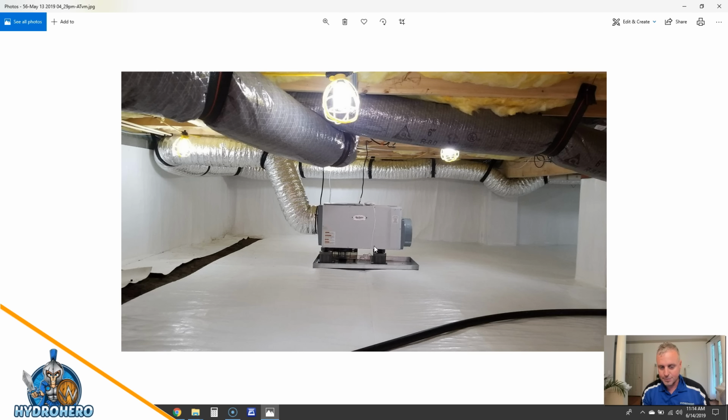We got this dehumidifier in here, our Aprilaire 1850. We got that installed with a moisture monitor in here and a leak detector, and we got it in our specialty pan. That way, if this condensate pump fails, which would be the main failure point in this crawl space, it'll hit this string and alert us via text or email, and a pop-up message on the customer's phone as well, so we can fix the problem before the water spreads all out in all different directions. You've got plenty of time before that happens. But we want to get that humidity under control as fast as possible.